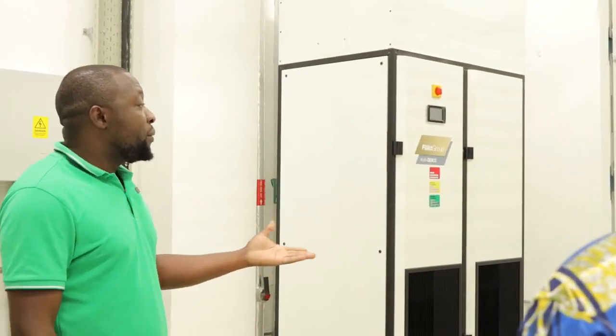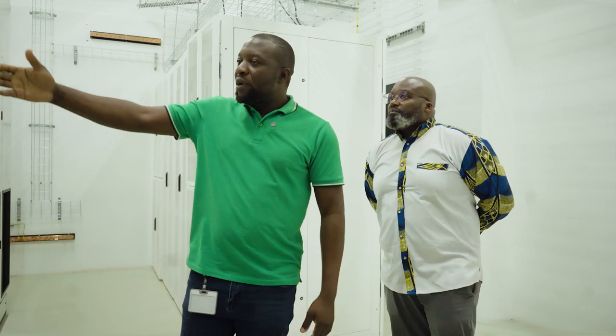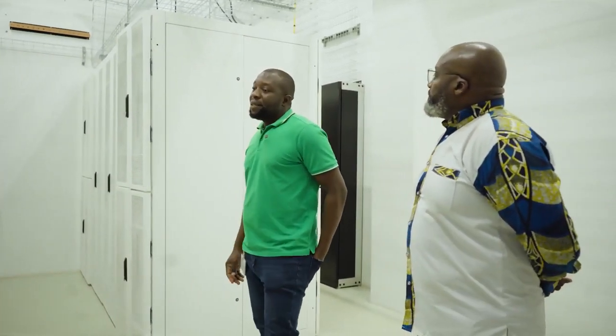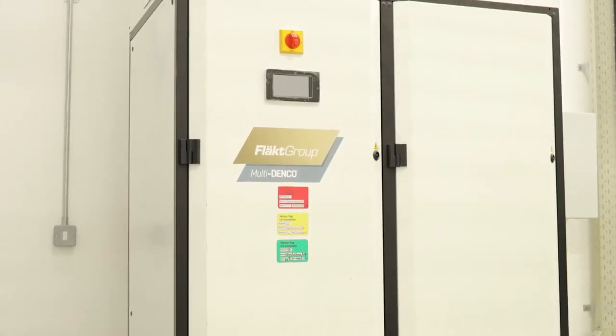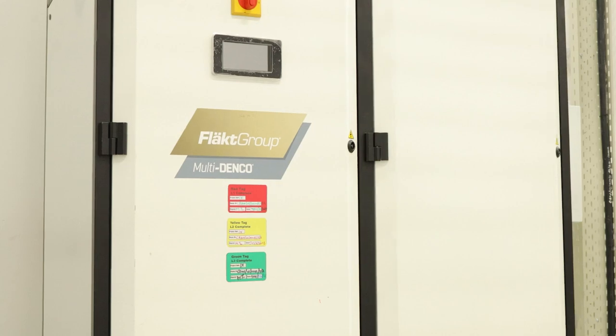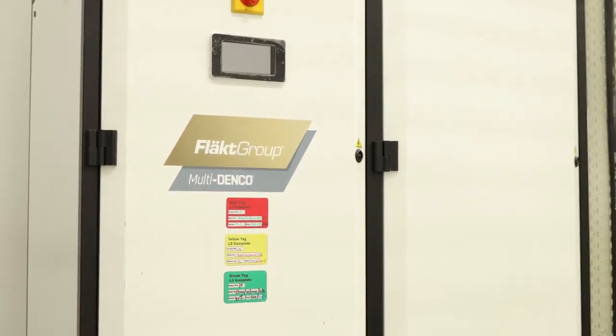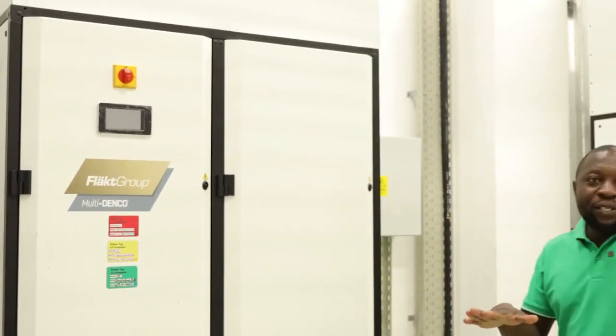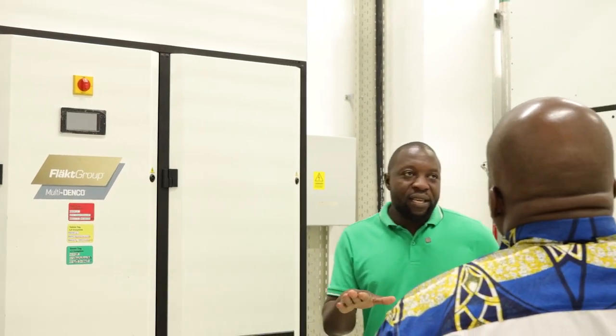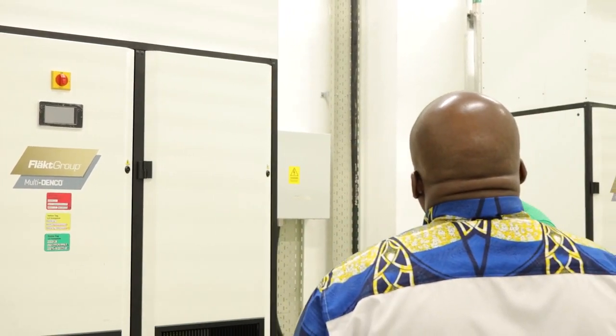In terms of cooling, some of the equipment here is active equipment and some is passive equipment. Active equipment requires cooling because it consumes power, and we have cooling equipment here. They are called CRAH units, computer room air handlers. They have two modes. One of the modes is a free cooling mode, which uses just general water. The other line is a DX system, a direct expansion system, which uses refrigeration and compressors. In this particular room, the temperature is set at 24 degrees Celsius. That's the optimum temperature for cooling inside this room.